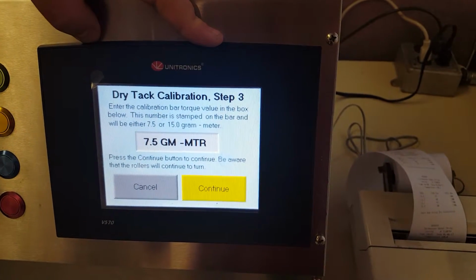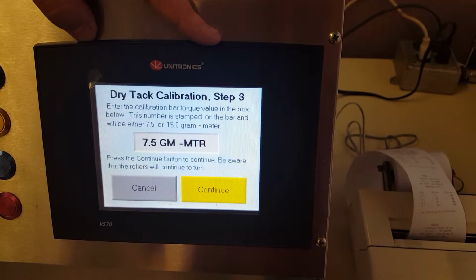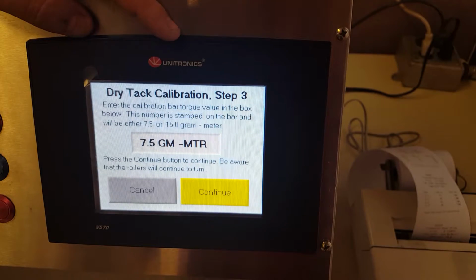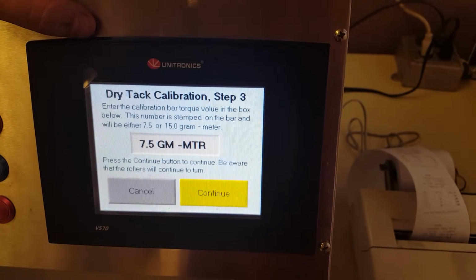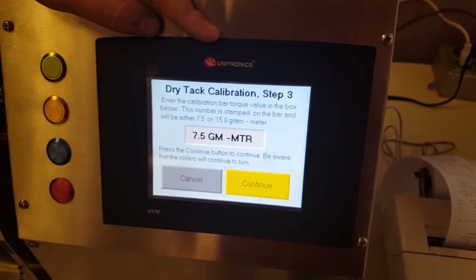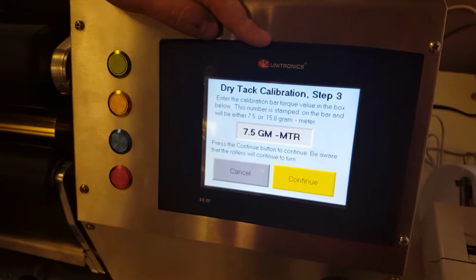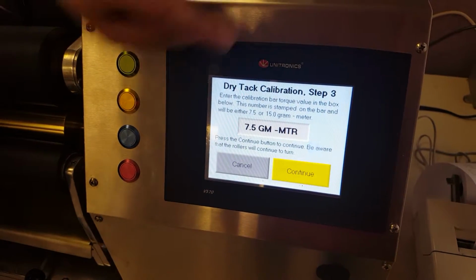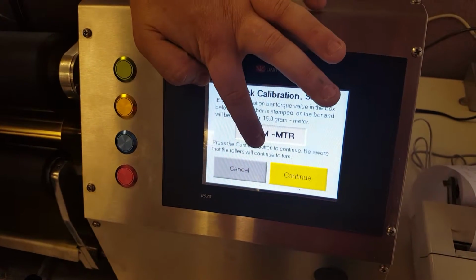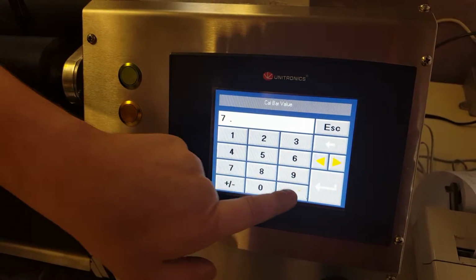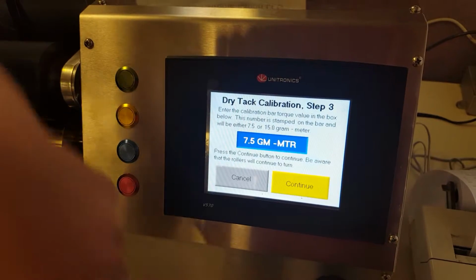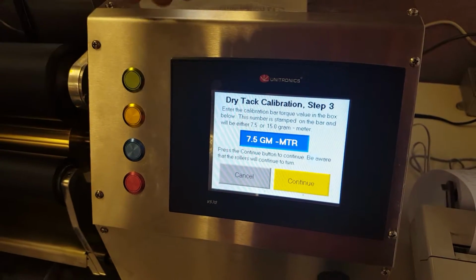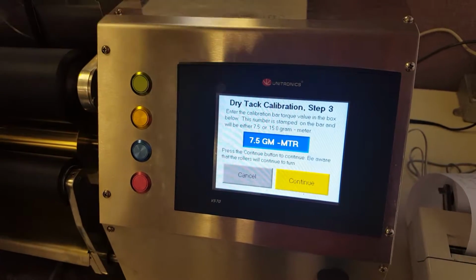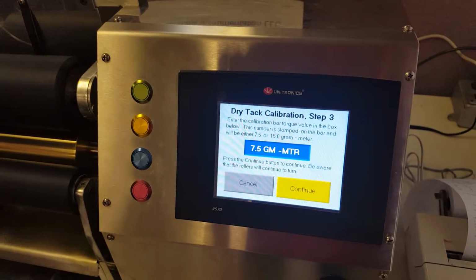and we get to our second screen of text, simply stating that we're going to hang our weight on this device and calibrate to it. What's important about this is that these bars generally come in a 7.5 or a 15 gram meter bar, but some people do have some slightly different ones, and you can toggle between that simply by touching and putting in whichever number you want, which I will do 7.5. So if you have a 7.5 or a 15 or a 20 or whatever it may be, this is the place where you want to tell the machine which one you're using.